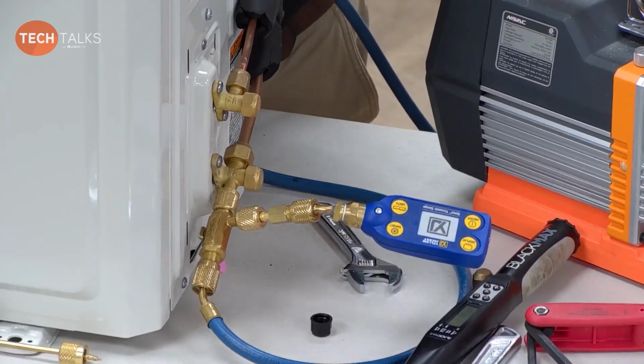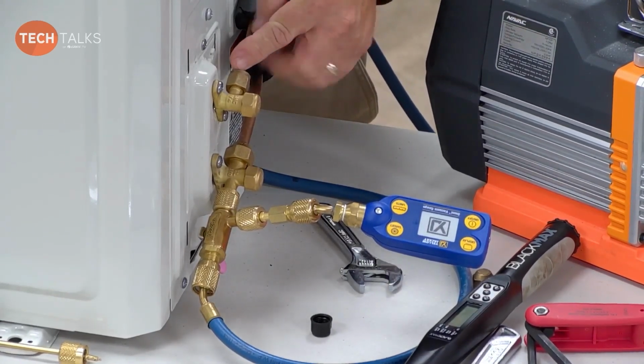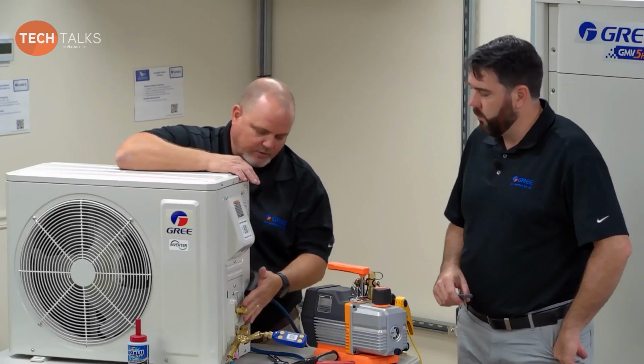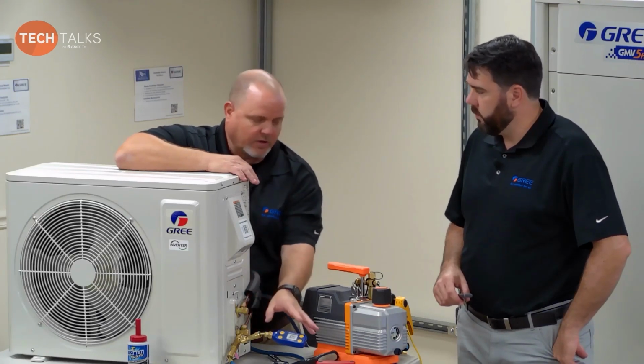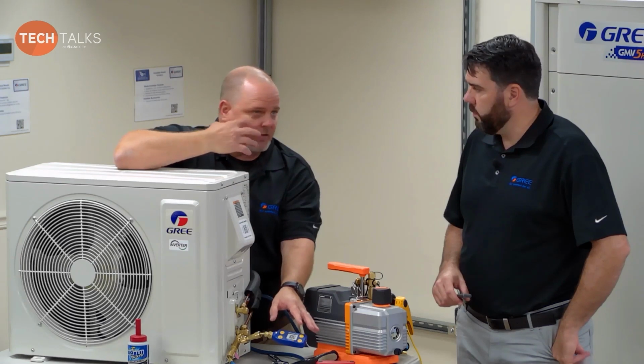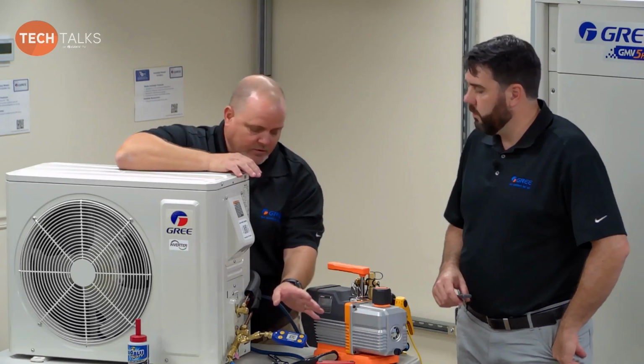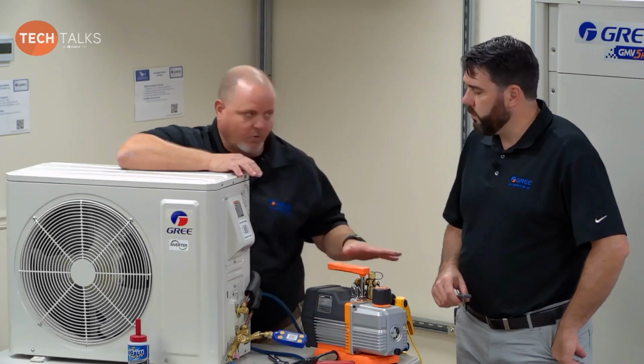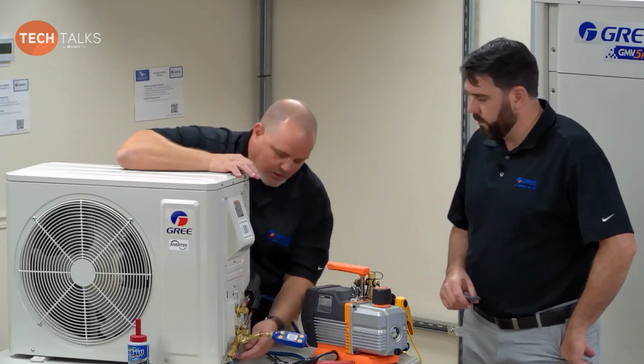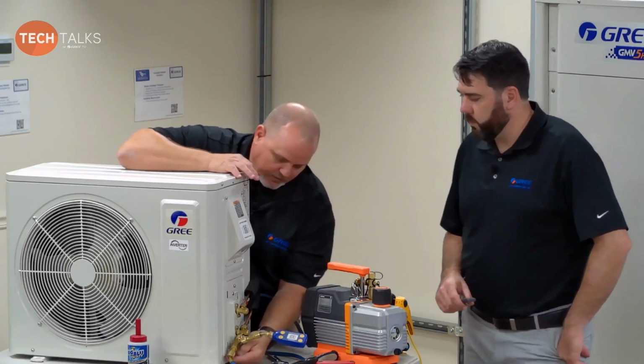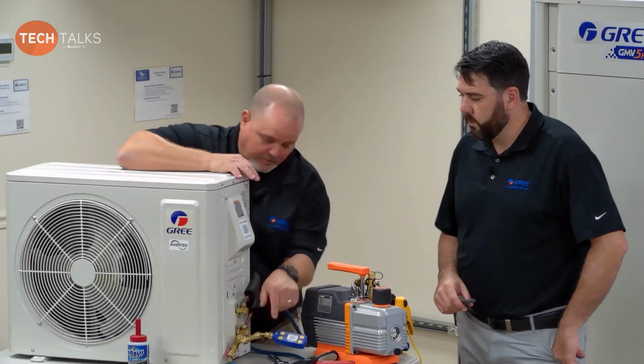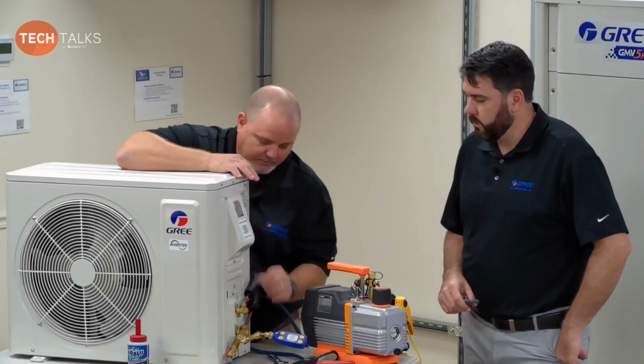It's going up through the indoor coil, coming back on the smaller line. We're evacuating both sides. So now we've reached our 500 microns. We know we're down. So now the first thing we're going to do, before we even shut the pump off, is we're going to take that valve. Now obviously this valve would have been open doing that. We're pulling down everything. We're down to 500 microns.